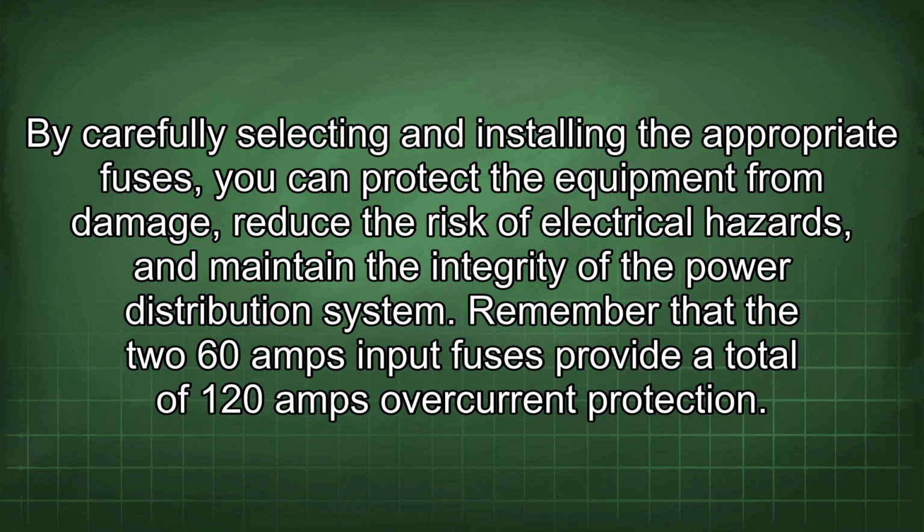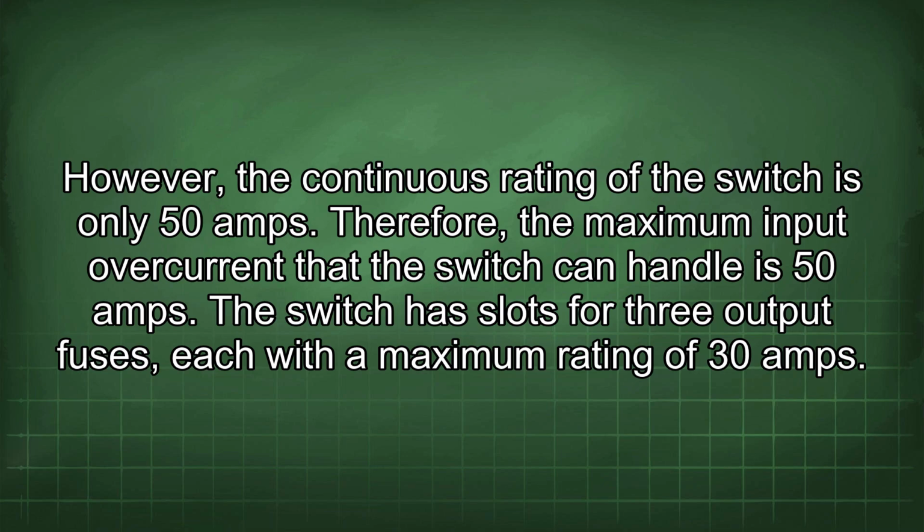Remember that the two 60 amps input fuses provide a total of 120 amps overcurrent protection. However, the continuous rating of the switch is only 50 amps. Therefore, the maximum input overcurrent that the switch can handle is 50 amps.